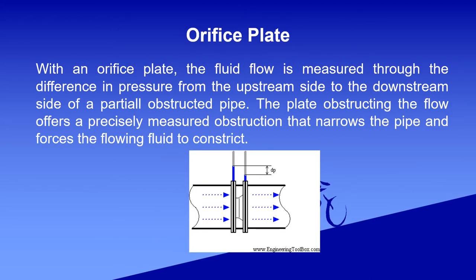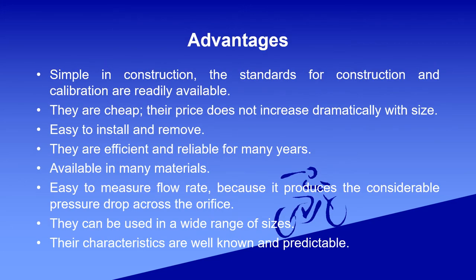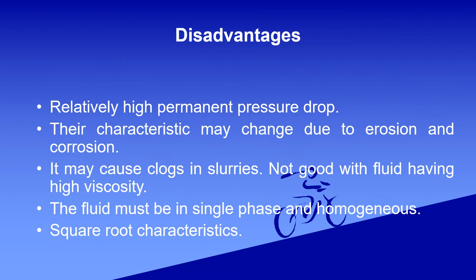The first one is the orifice plate. The fluid flow is measured through the difference in pressure from the upstream side to the downstream side. The advantages of the orifice plate include: simple in construction, cheap, easy to install and remove, efficient and reliable, available in many materials, easy to measure flow rate, can be used in a wide range of sizes, and its characteristics are well known and predictable.